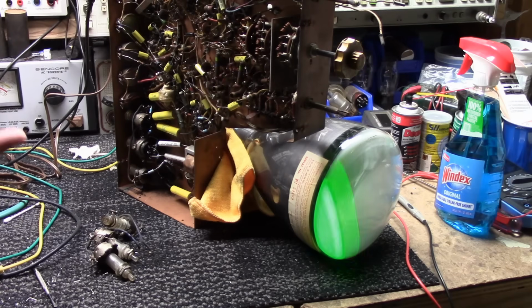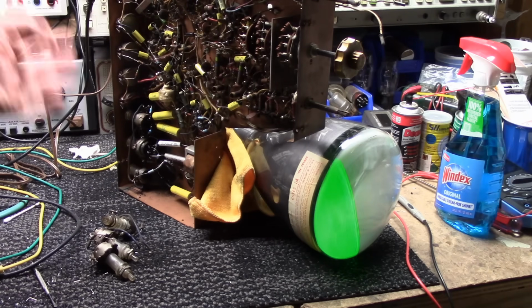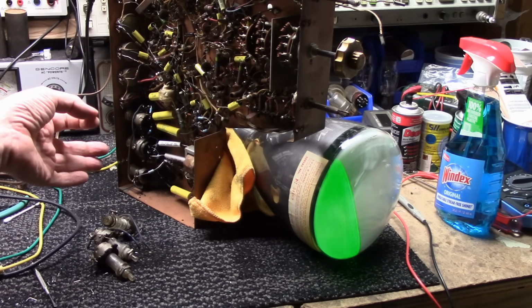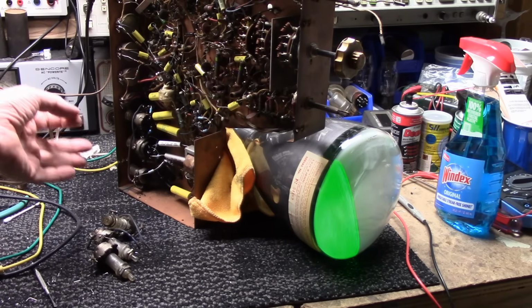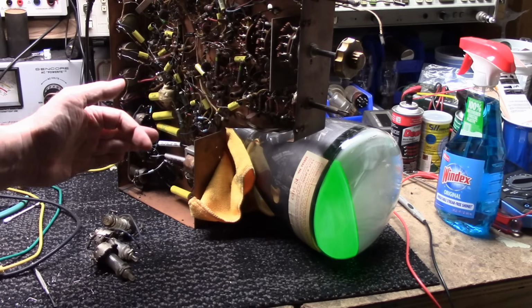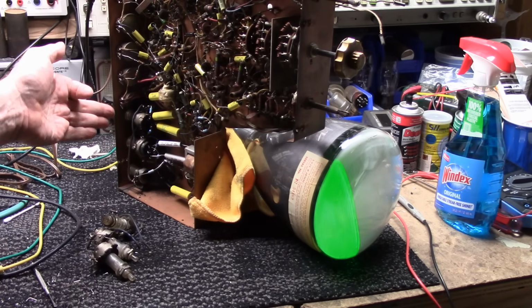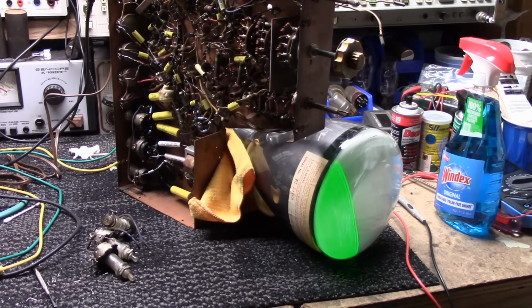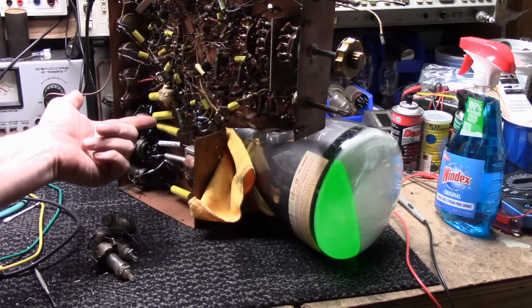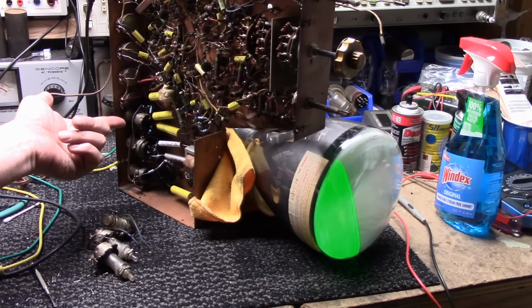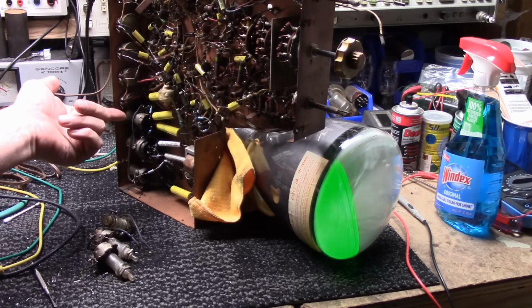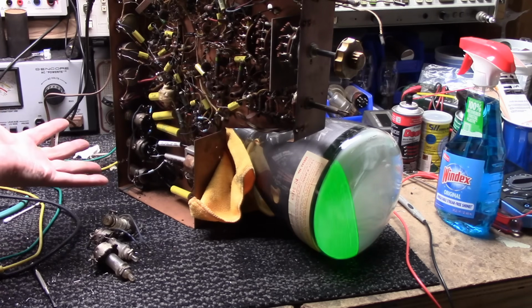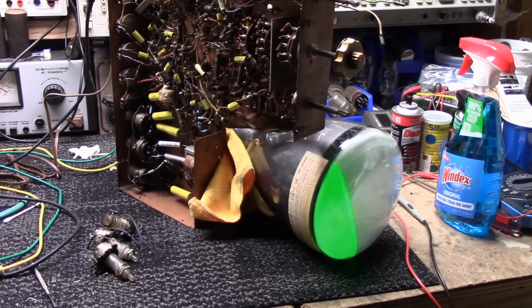Now, it could be a couple things. One, there was a problem with the control and it was arcing inside, maybe tin whiskers. Or it's arcing somewhere else, which caused the damage to the control. So maybe that cap shorted out, causing the control to fail, or the control failed on its own due to internal problems. We need to figure out exactly what the problem is and remedy it.